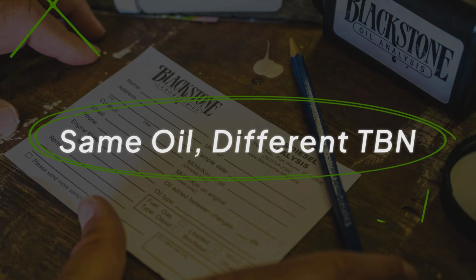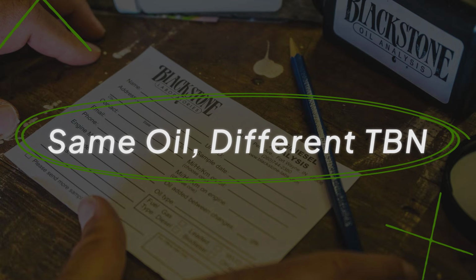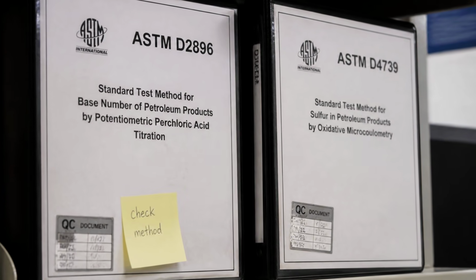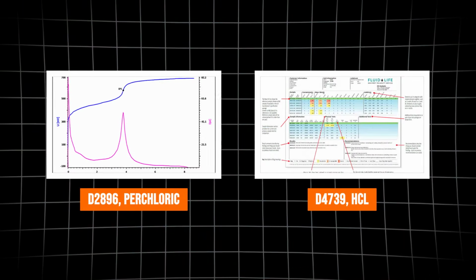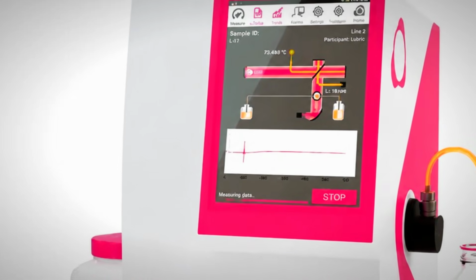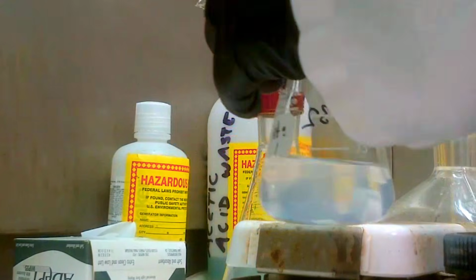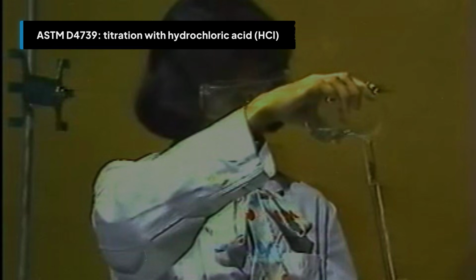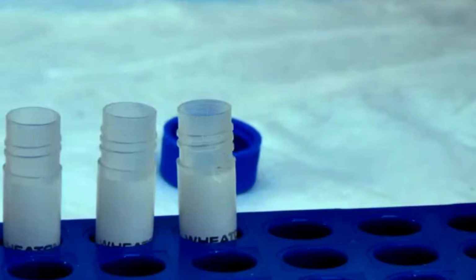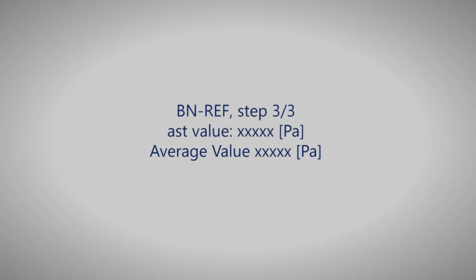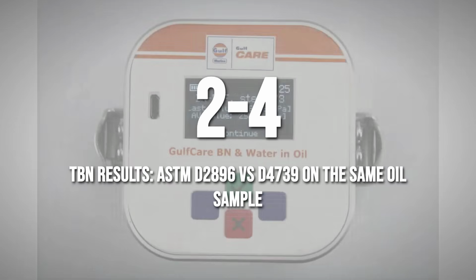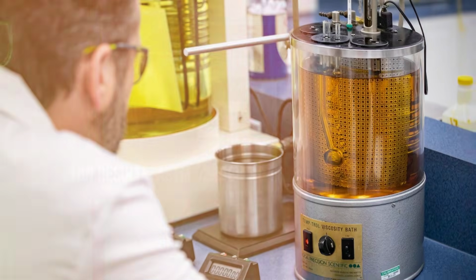There is also a measurement problem that most used oil analysis customers never encounter in the instructions. Two ASTM test methods exist for measuring total base number, and they disagree. ASTM D2896 uses perchloric acid as the titrating agent. ASTM D4739 uses hydrochloric acid. Run the same oil sample through both tests and the total base number values can differ by 2 to 4 units.